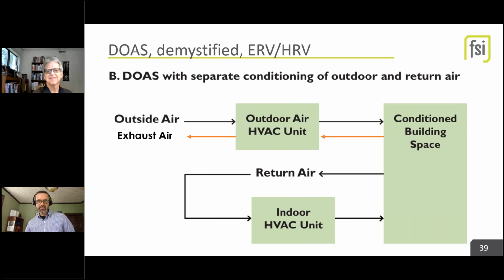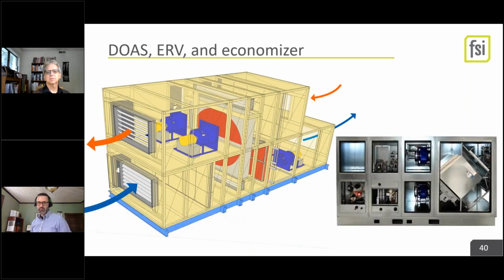Next slide. So this is a unit, and it's got all of the parts we're talking about. So I'm going to point them out. That orange circular thing is heat recovery. That's an enthalpy wheel. The purple and yellow things that you see on both sides of that enthalpy wheel are respectively supply fans for the incoming air, the outside air fans, and the exhaust fans for the air leaving the building. And it moves over the two sides of that enthalpy wheel to move energy around. If you look above and below that orange circle, you've got little dampers that are giant, super skinny rectangles, that allows you to bypass the energy wheel and do an economizer function.